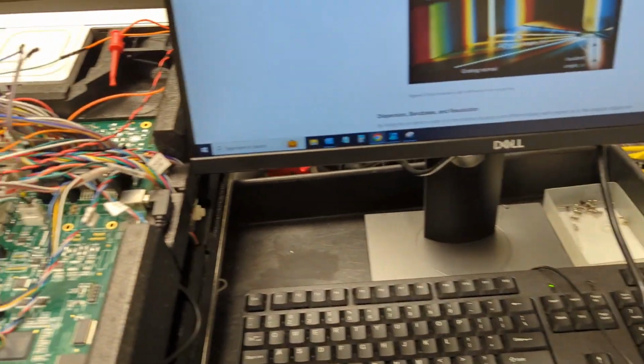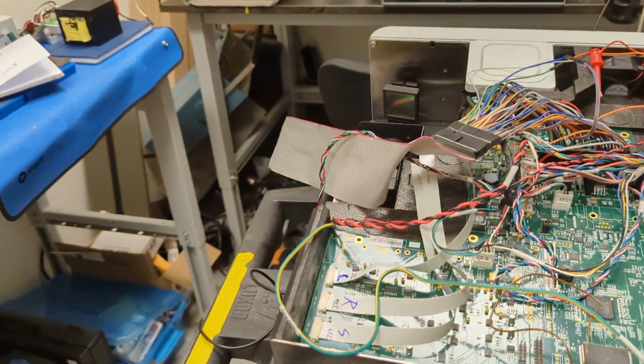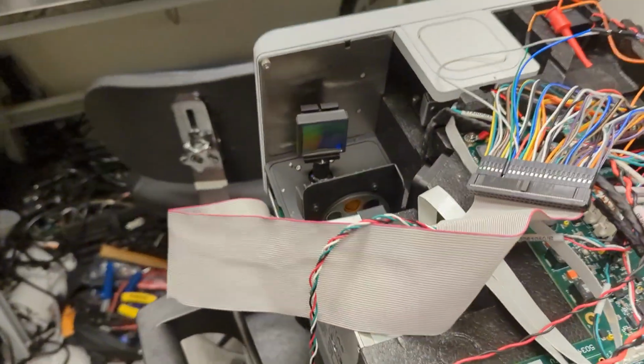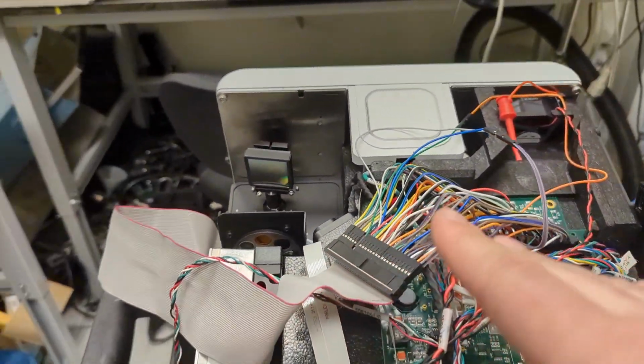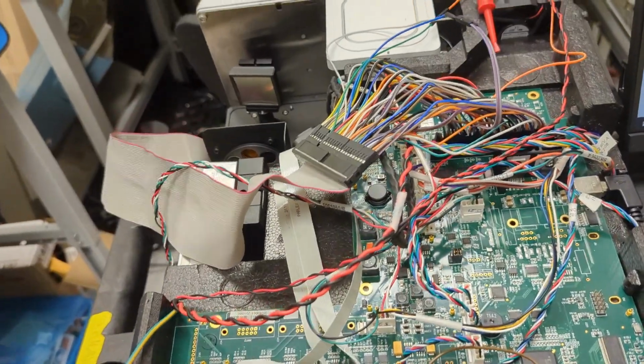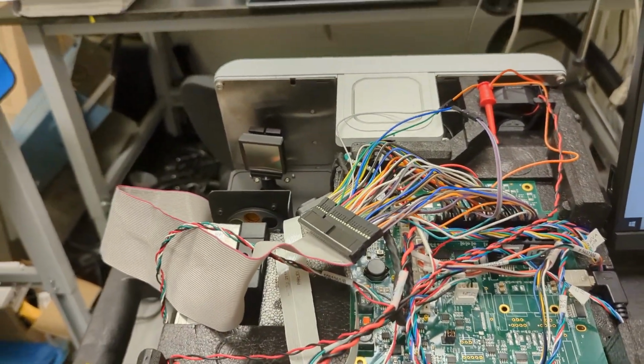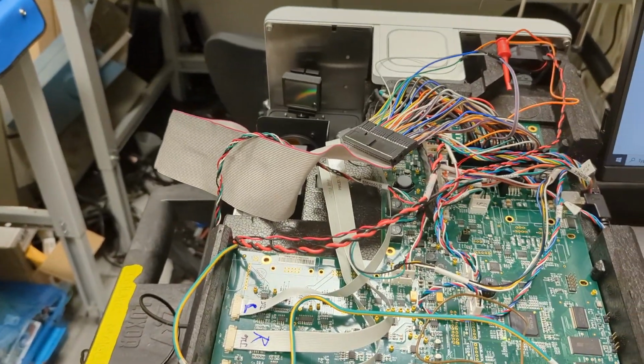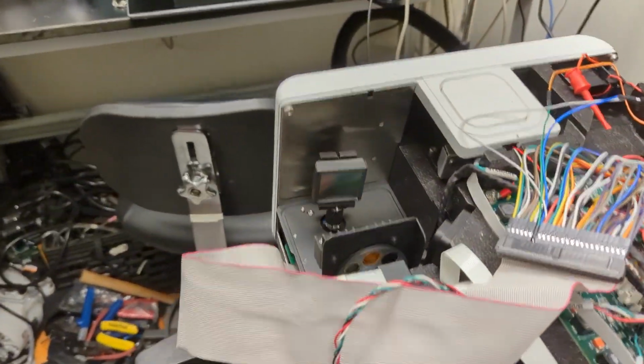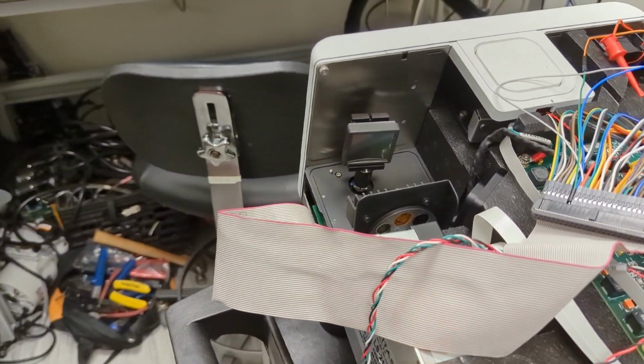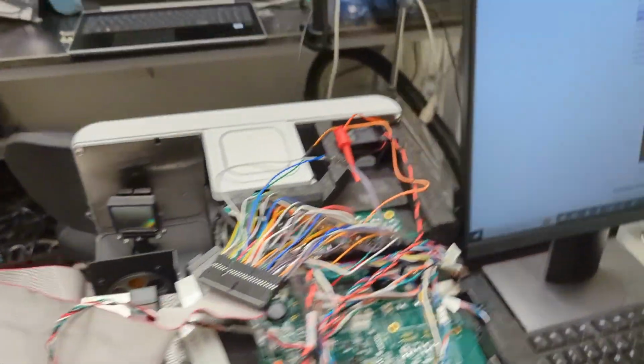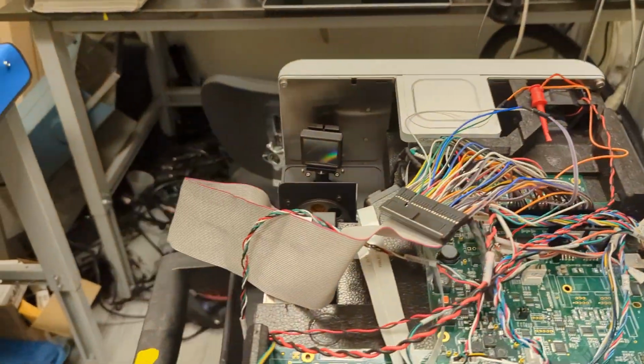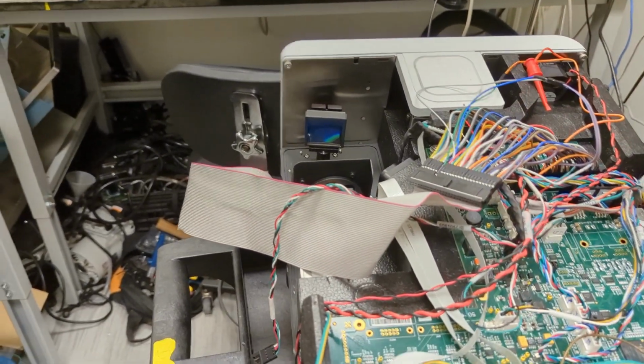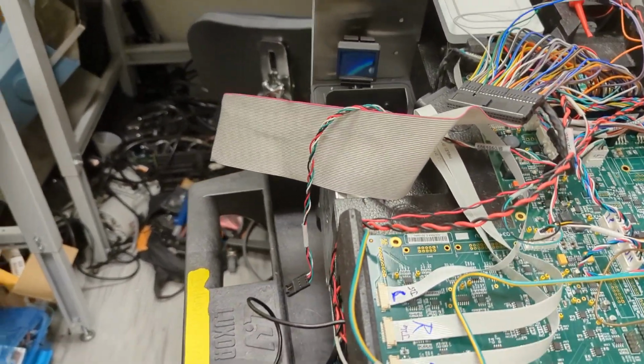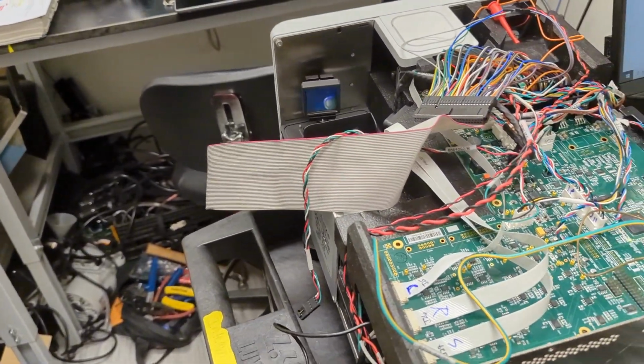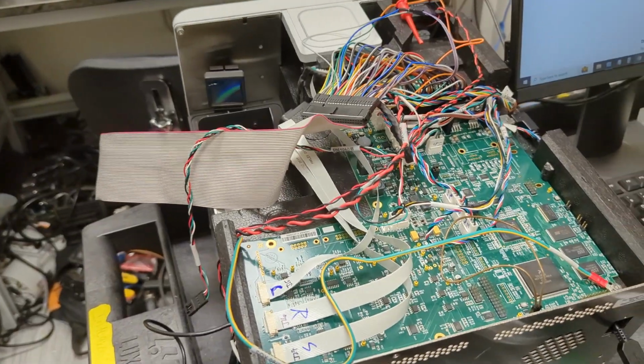You're going to need that. And another thing that I did want to mention, I'm kind of all over the place here, and I apologize for that, but you'll see that I've got all of these wires all over the place, right? So I wanted a way to keep the lamp on as long as I wanted, because it's only on for a brief period of time during the startup, and obviously when you're running an experiment. You don't have any way in the software of just manually turning the lamp on or off. There's nothing like that here. So I had thought of powering it externally, which didn't work. The instrument wasn't happy with that.